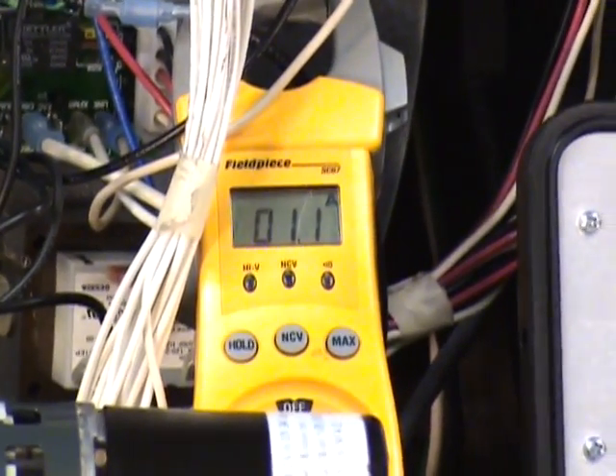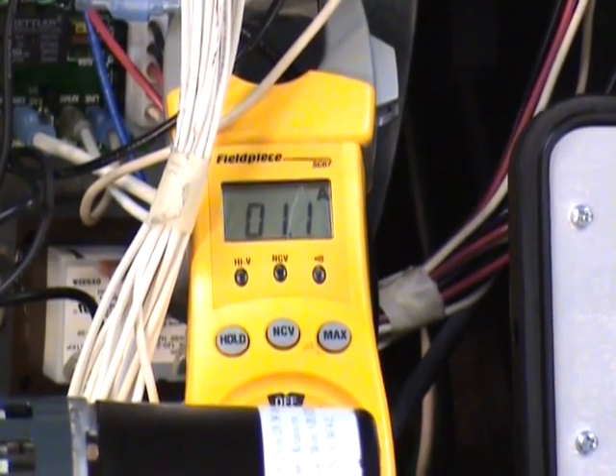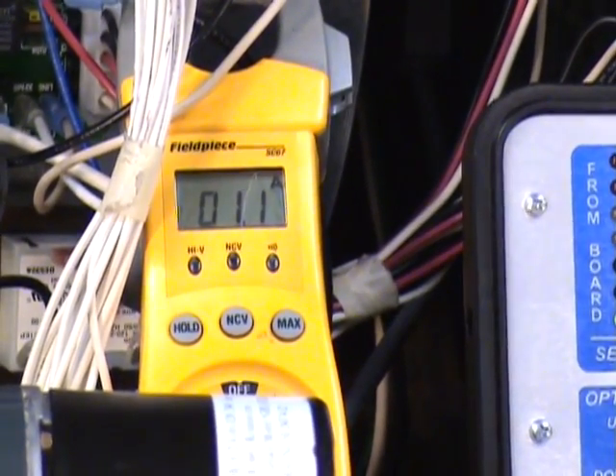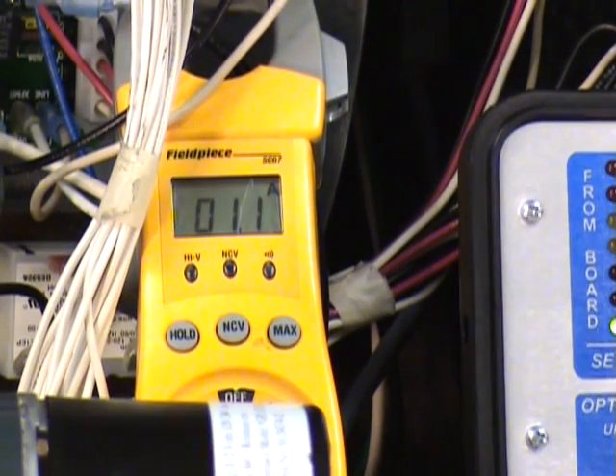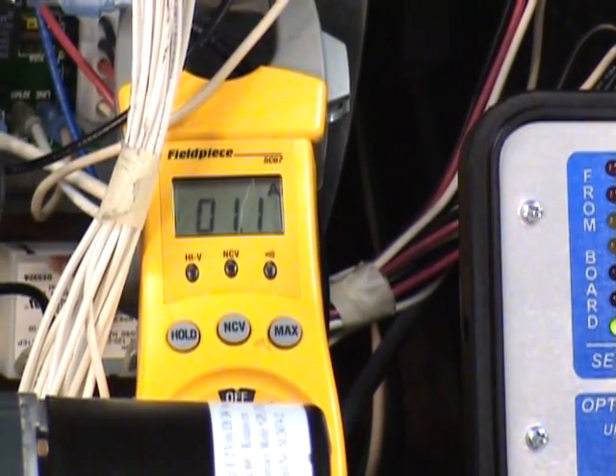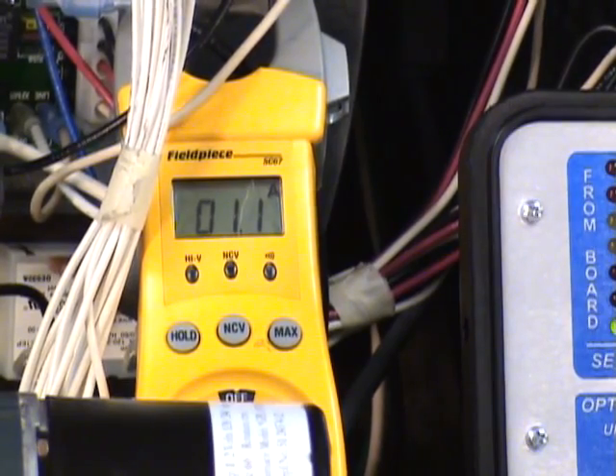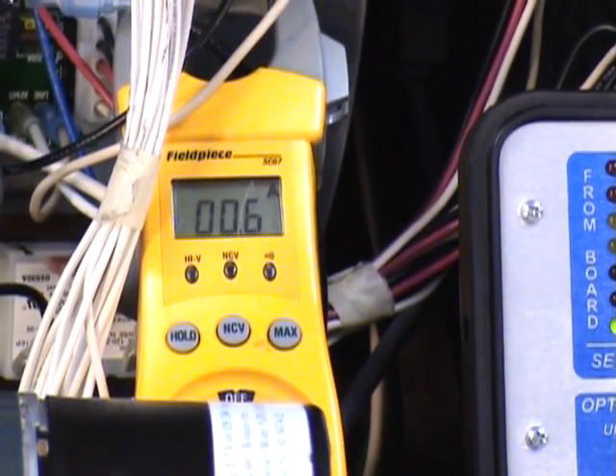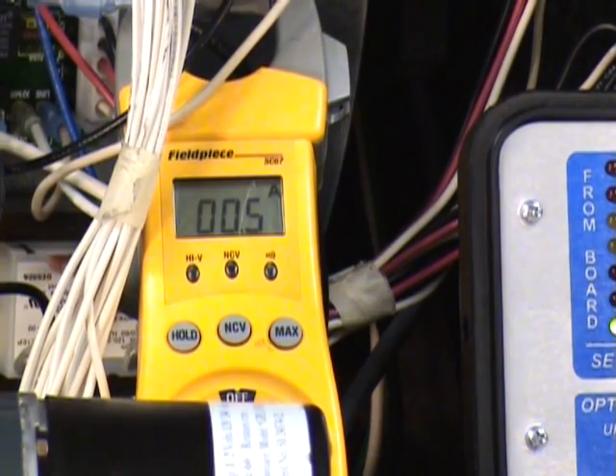Focus over here on this meter, please. That meter isn't the most accurate in the lower ranges, but it's telling us that the motor is drawing 1.1 amps. It's hard to see the decimal point, but it's in there. 1.1 amps, and stay focused right where you are. I'm going to remove that restrictive cover that's putting external static pressure on our system. The motor slows down, and you can hear it slow down. Now can you see the display? It's drawing right at half an amp. So it more than doubled the amp draw when the restriction in the system goes up.